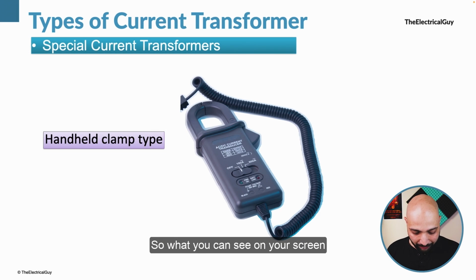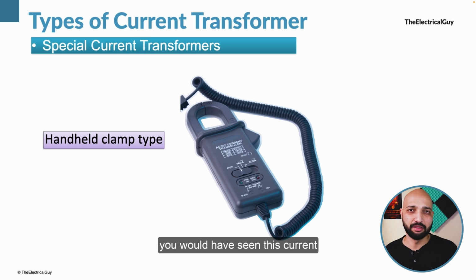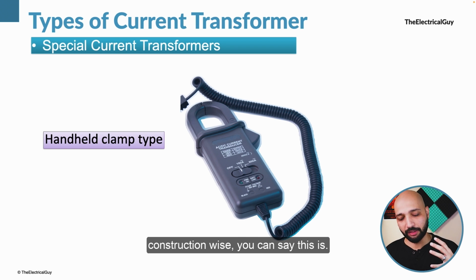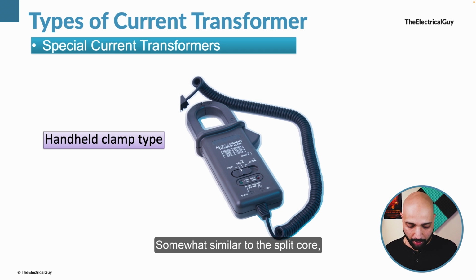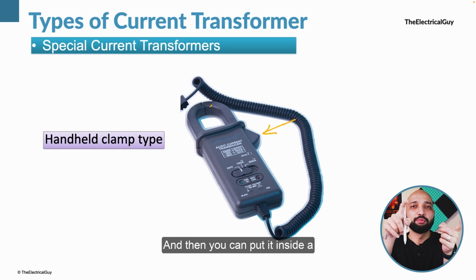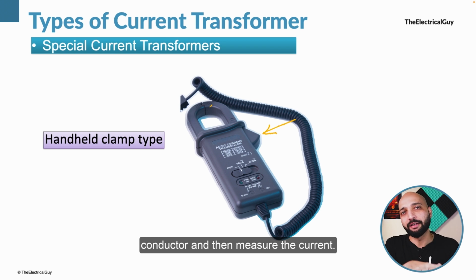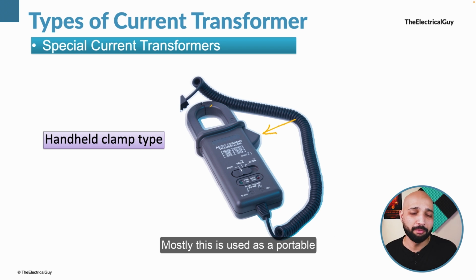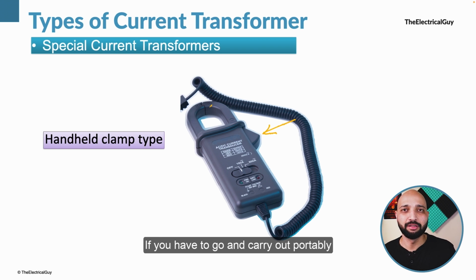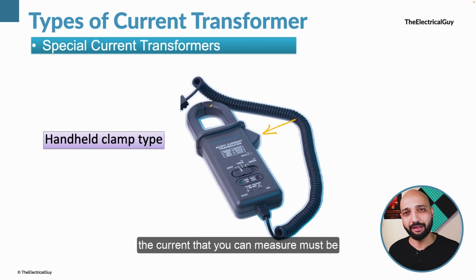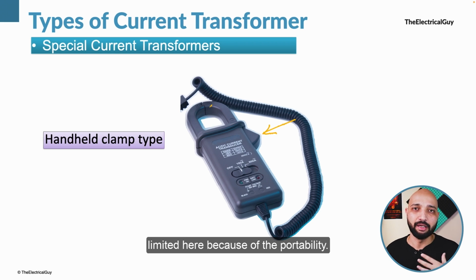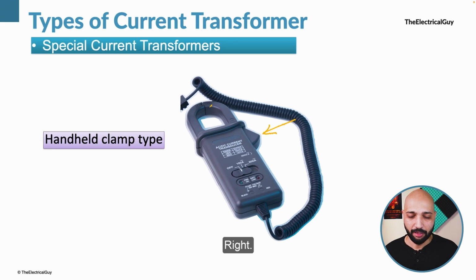So what you can see on your screen is a handheld clamp type. Now you would have seen this current transformer very frequently used. Construction wise, you can say this is somewhat similar to the split core, because when you press this lever here, these cores get split, and then you can put it around a conductor and measure the current, right? Mostly this is used as a portable current transformer, and it is not fixed permanently. If you have to go and carry out measurements portably, you can use this type. But of course the current that you can measure must be limited here because of the portability, right? That is the handheld clamp type current transformer.